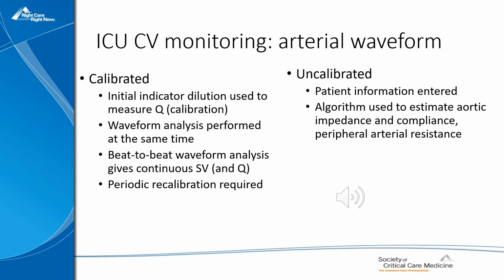As I've mentioned, in calibrated devices such as VolumeView, PiCCO, or LiDCO Plus, an indicator is initially injected to calibrate the device, and then beat-to-beat information about stroke volume and cardiac output is provided by waveform analysis that is performed at the same time as the initial indicator dilution test. Periodic recalibration is required to make sure that the waveform analysis remains accurate when it represents the stroke volume and cardiac output.